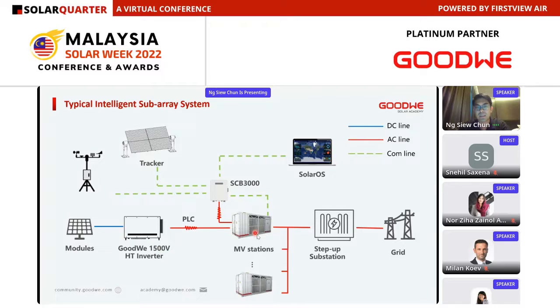Our output for the inverter is 800 volt AC, and we can step up to 11 kV or 33 kV depending on the project, then to the step-up substation and grid. Our communication data logger, besides communicating with our inverter via PLC, also supports fiber optic cable communication directly with the central control station, where your PPC and SCADA may be located.